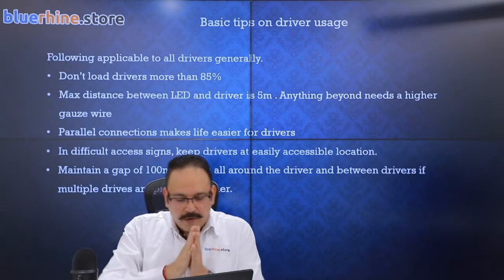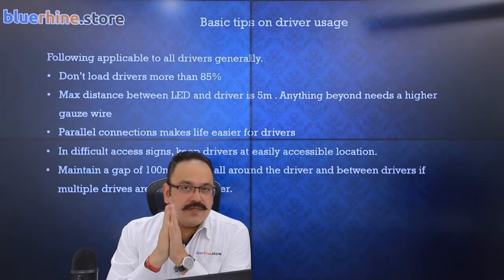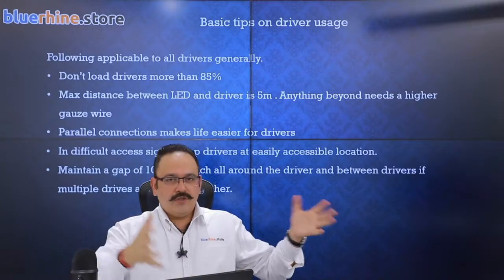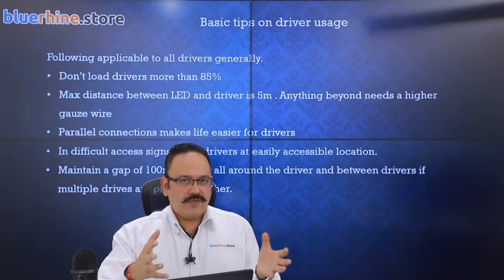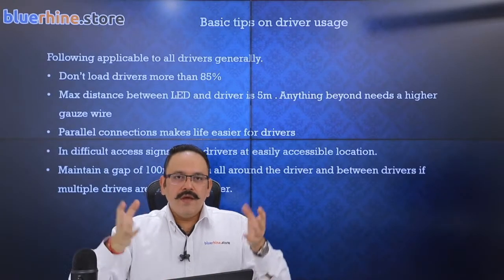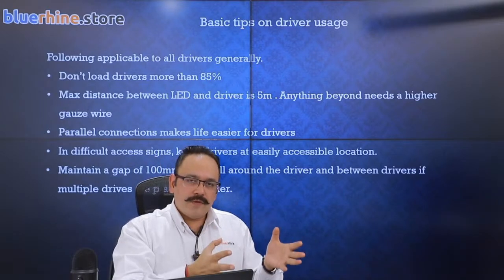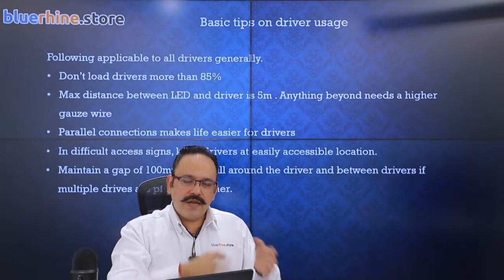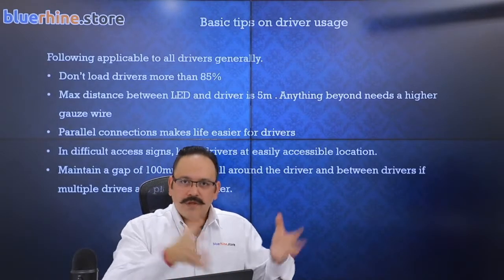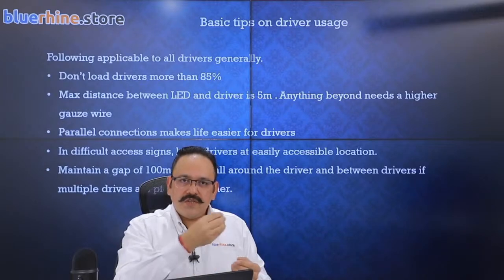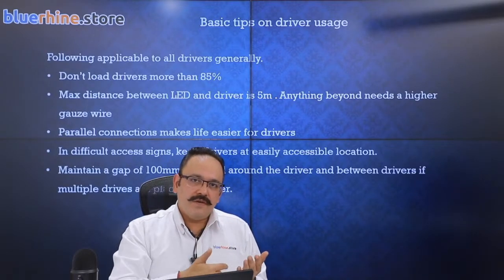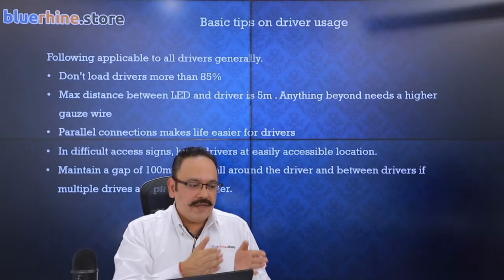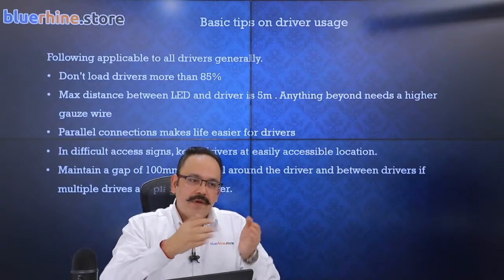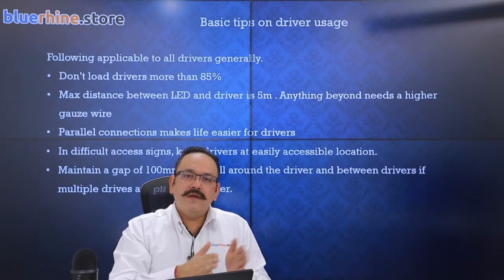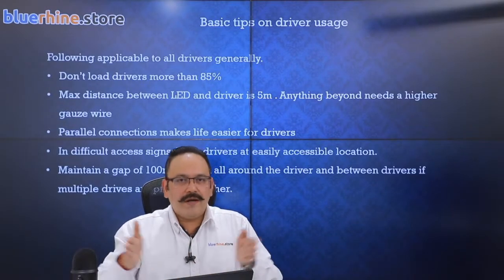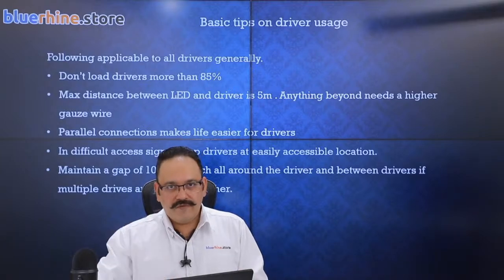Another aspect on bigger signs: we often have a bunch of power supplies or transformers used together. We put all those transformers together in the junction box, holding them close together. But these transformers interfere with each other, so let's avoid that. Give at least a 100 gap in either direction between transformers - spread them out and you'll get longer-lasting transformers.